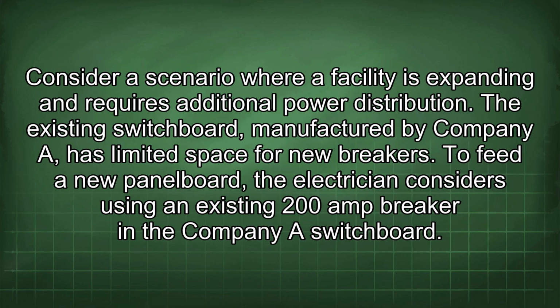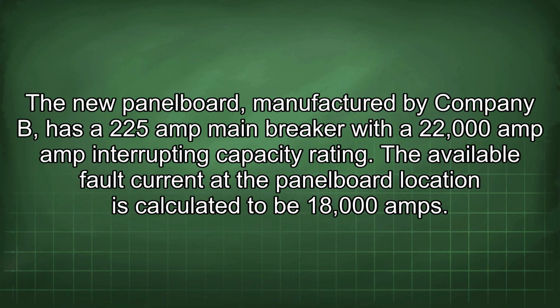Consider a scenario where a facility is expanding and requires additional power distribution. The existing switchboard, manufactured by Company A, has limited space for new breakers. To feed a new panel board, the electrician considers using an existing 200 amp breaker in the Company A switchboard. The new panel board, manufactured by Company B, has a 225 amp main breaker with a 22,000 amp interrupting capacity rating. The available fault current at the panelboard location is calculated to be 18,000 amps.